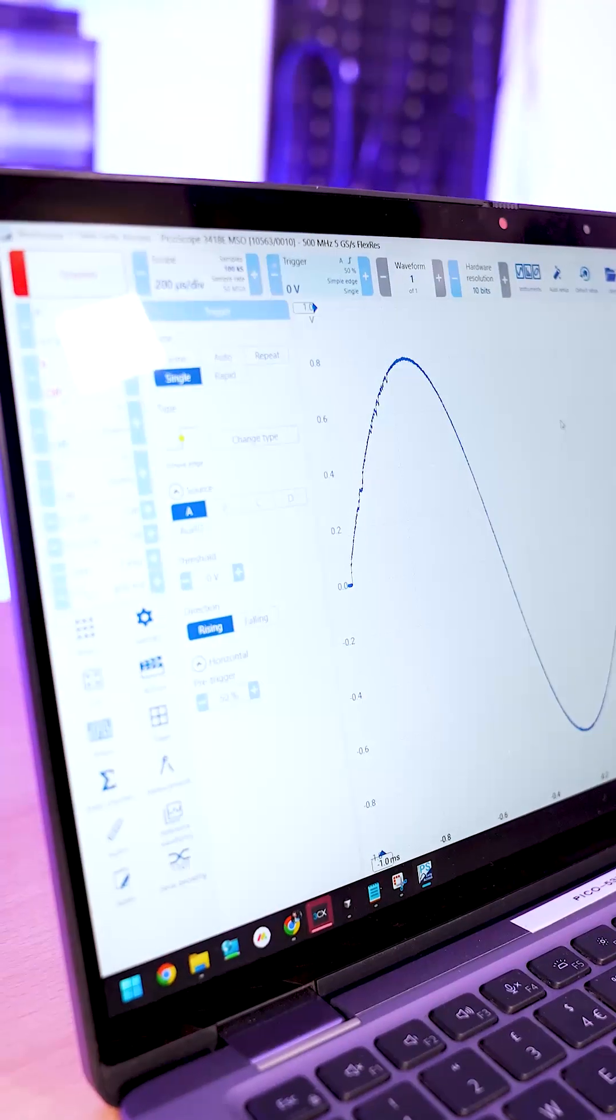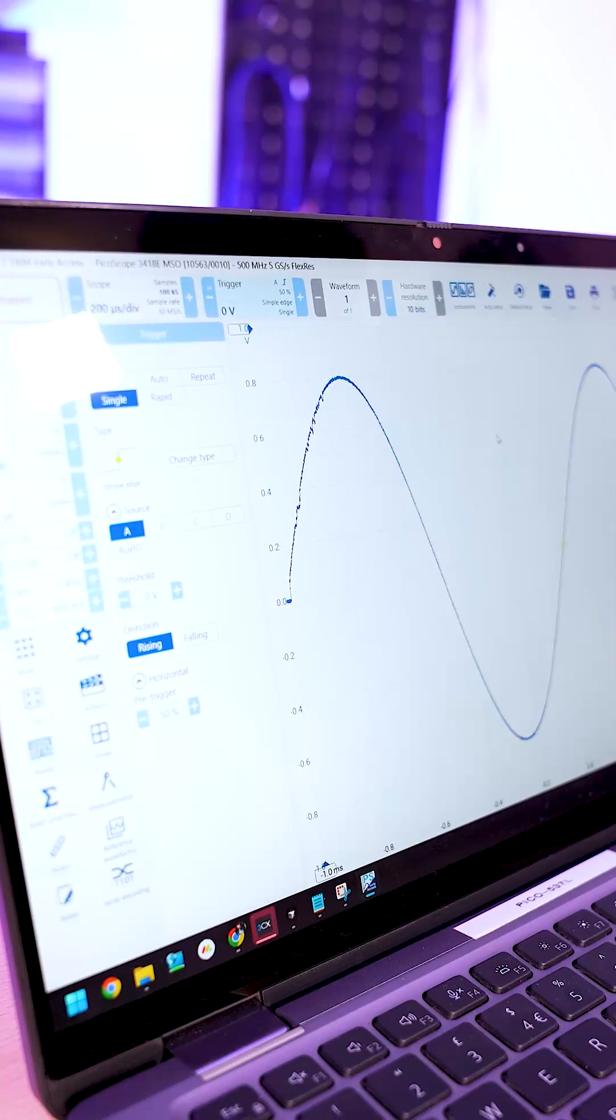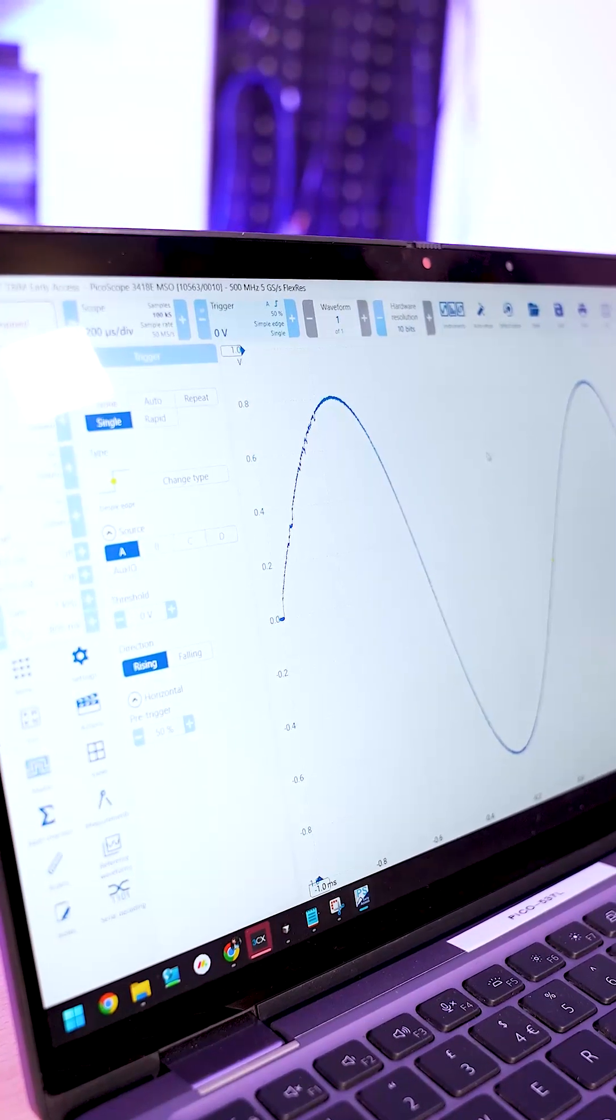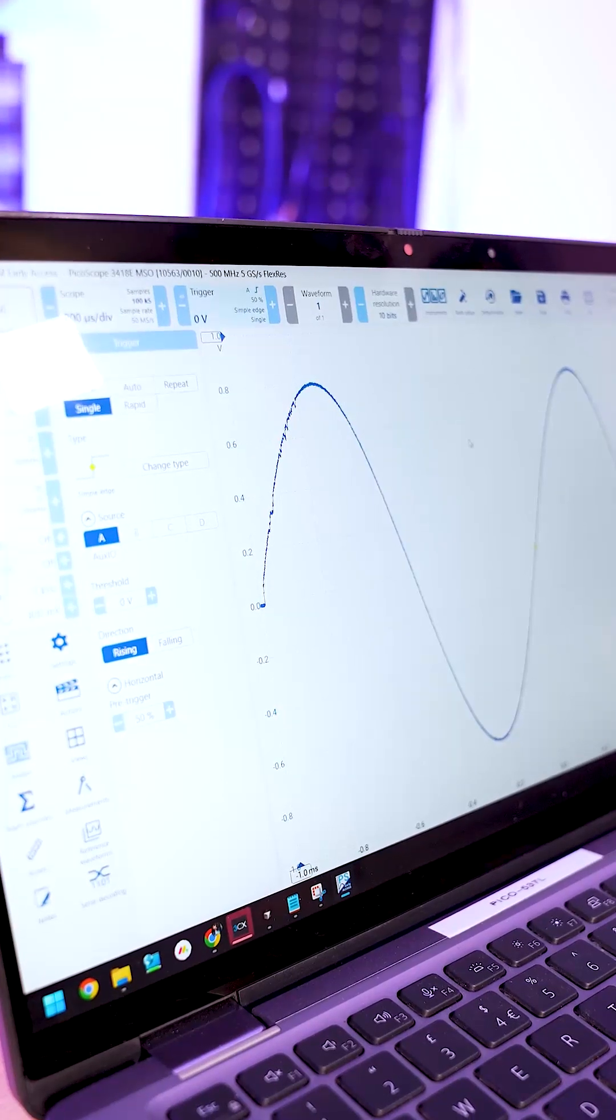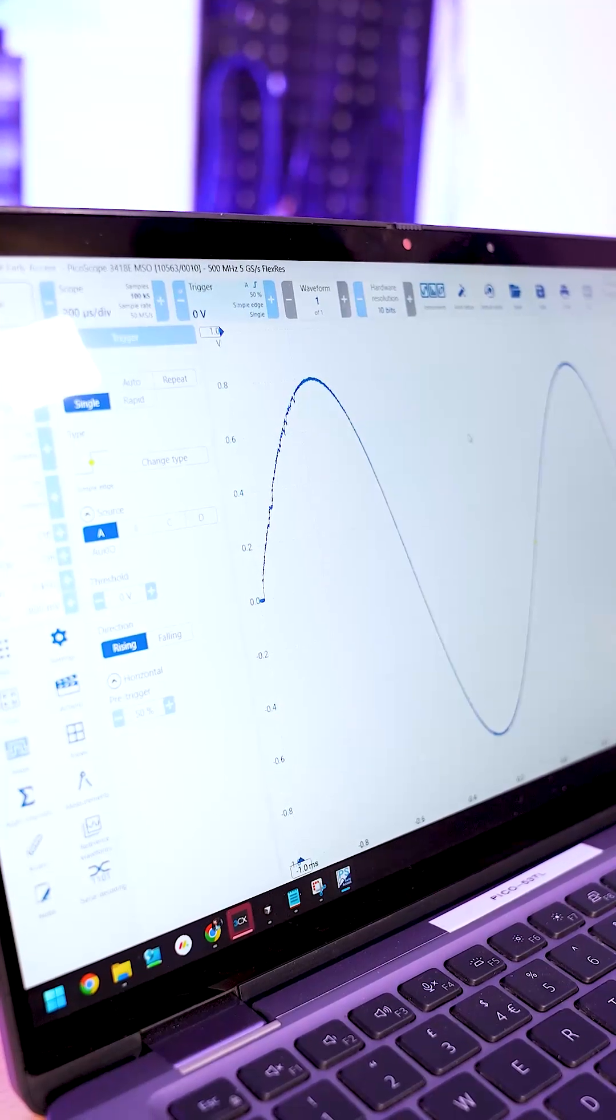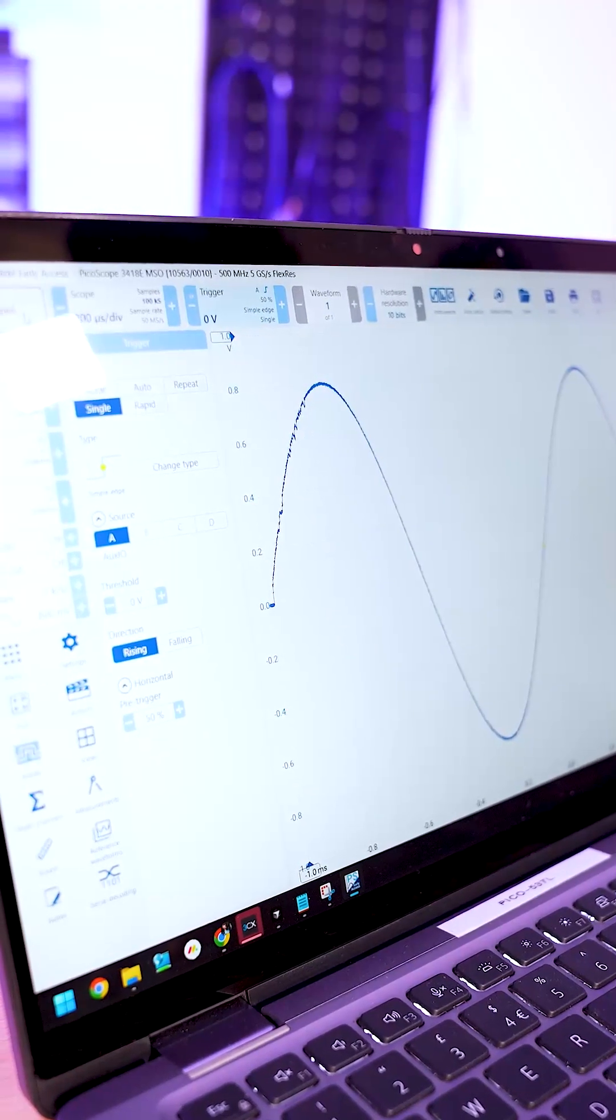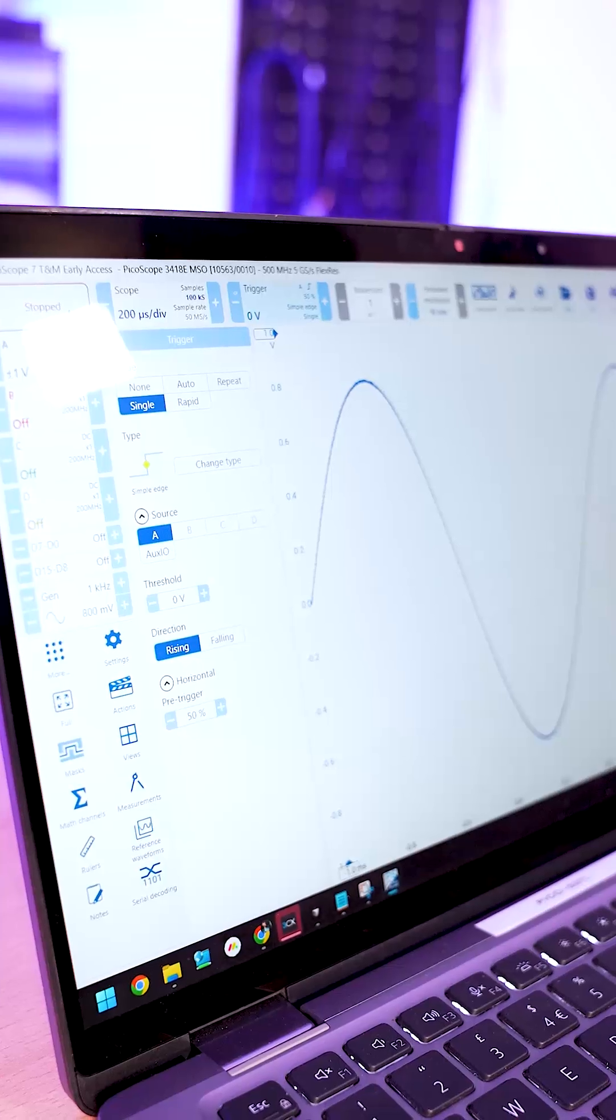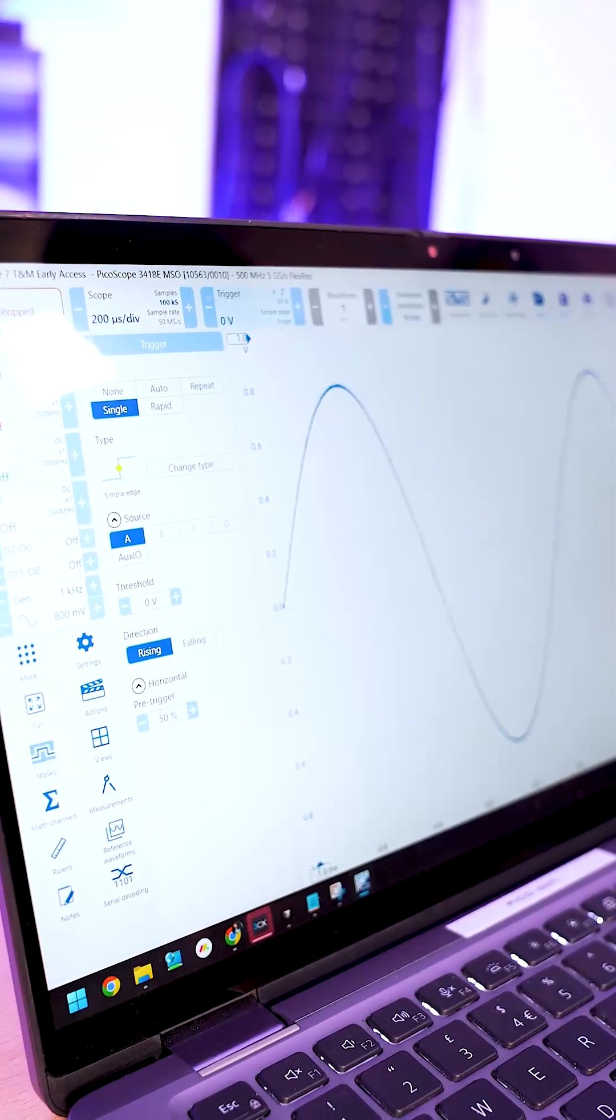As soon as we have a signal it would trigger and then you'll have the signal straight away. The important thing about single is it will only trigger once and to rearm it you need to rerun it and it will find the nearest trigger point.